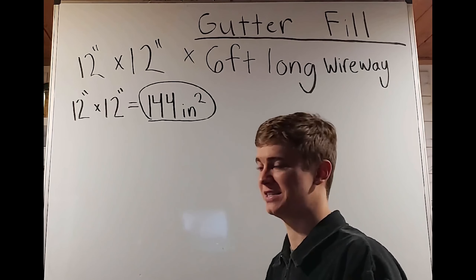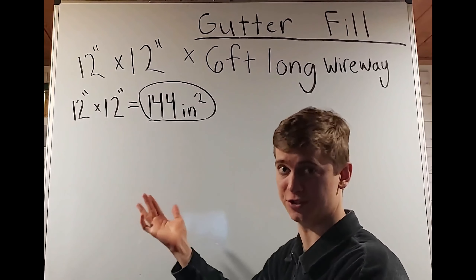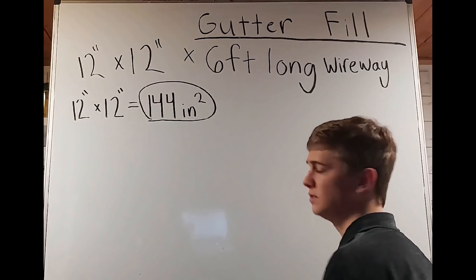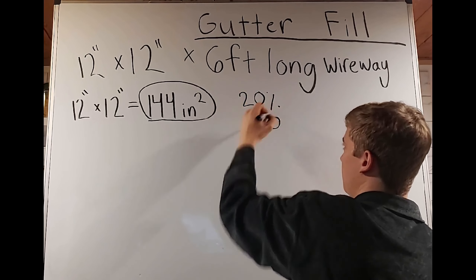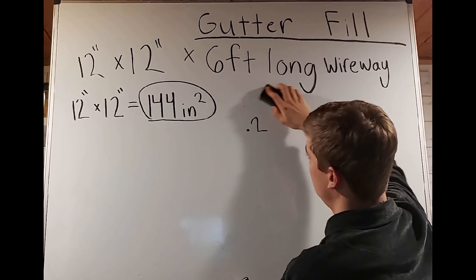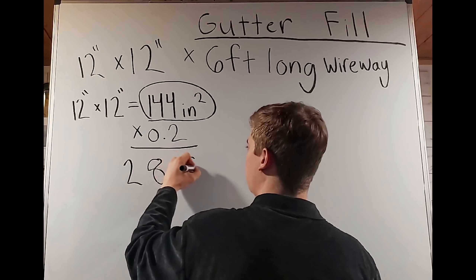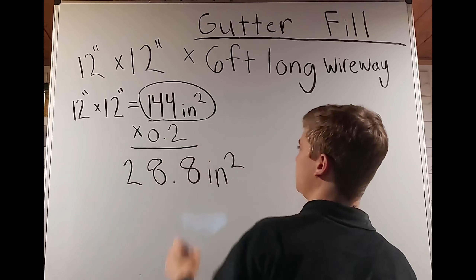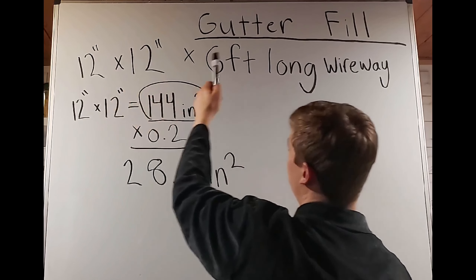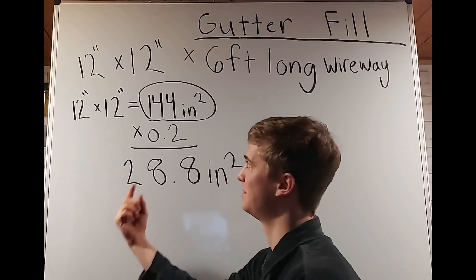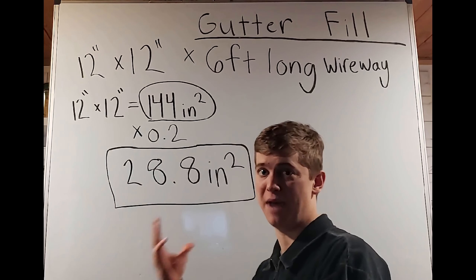We're not done yet with this 144 square inches because we can only fill it to 20%. Written as a decimal, 20% is 0.20 — or just 0.2. If we take 144 and multiply by 0.2, that gives us how much we can fill: 28.8 square inches. Remember, this is still square inches. This is the cross-sectional area that we can fill this 12-by-12-by-6-foot-long wireway. Simply: 12 inches times 12 inches equals 144, we take 20% of that, and that's the max fill for the wireway.